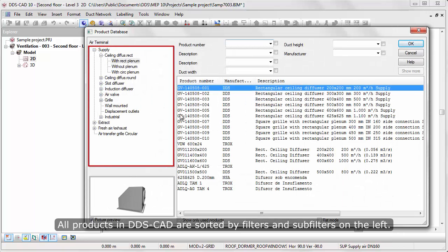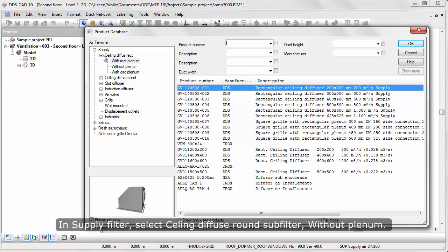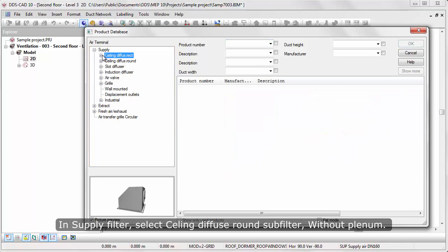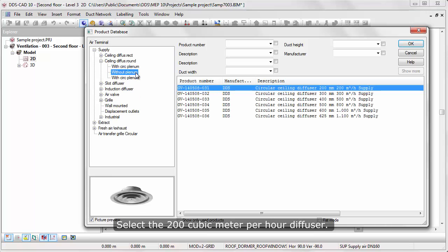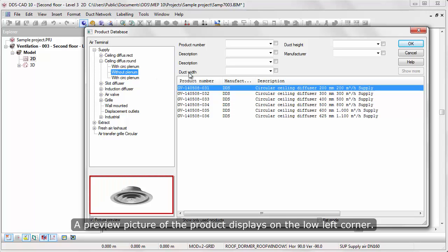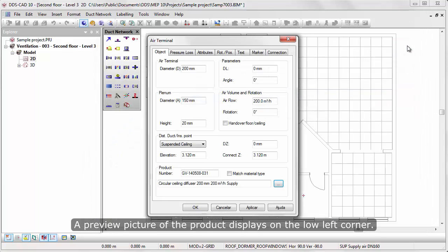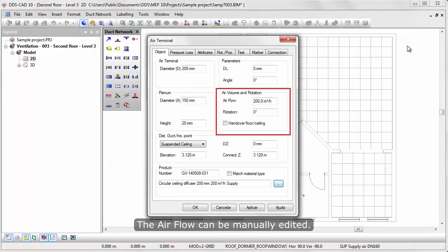All products in DDS-CAD are sorted by filters and sub-filters on the left. In Supply filter, select the Ceiling diffuser round sub-filter, without plenum. Select the 200 cubic meter per hour diffuser. A preview picture of the product displays on the lower left corner. The air flow can be manually edited.